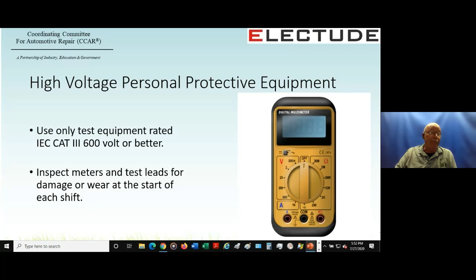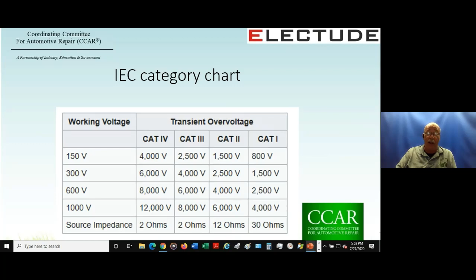This chart shows the maximum transient voltage protection for working voltage range. Now, we said Cat 3. The reason we're saying that is because you can also get a Cat 2 and a Cat 1. What you're not gaining is the over voltage transient protection. That's why we want a Cat 3 at 600 volts. That gives you a minimum transient over voltage protection of 6,000 volts.